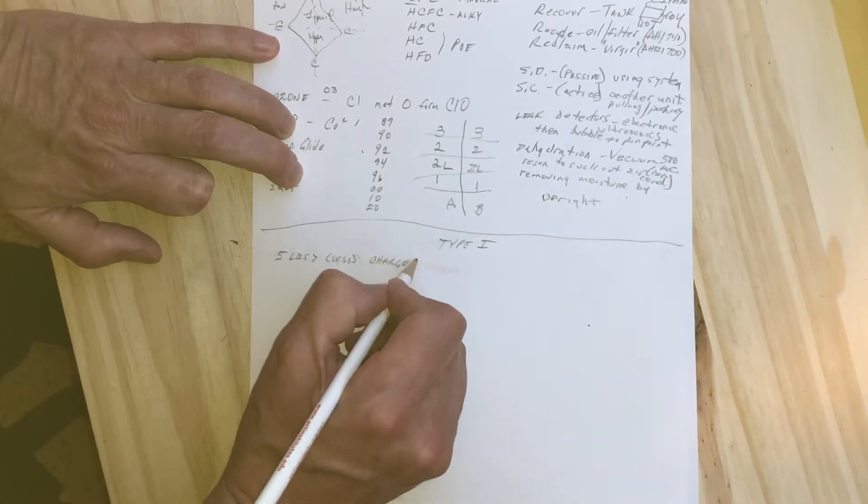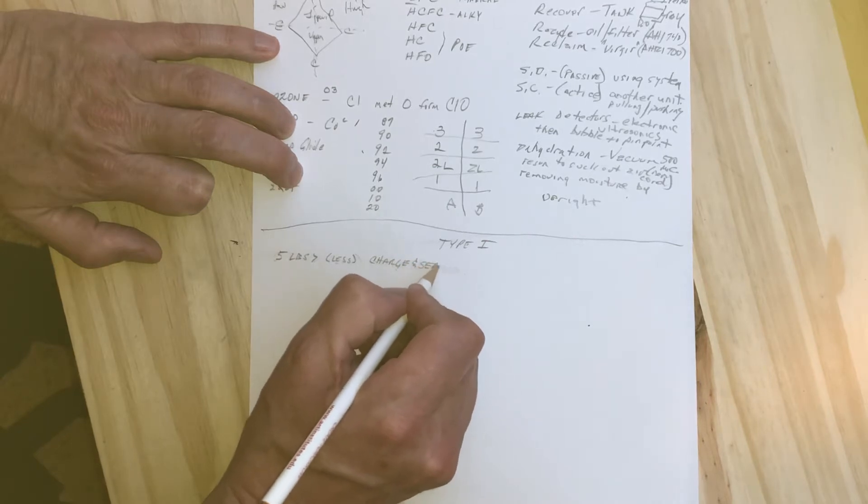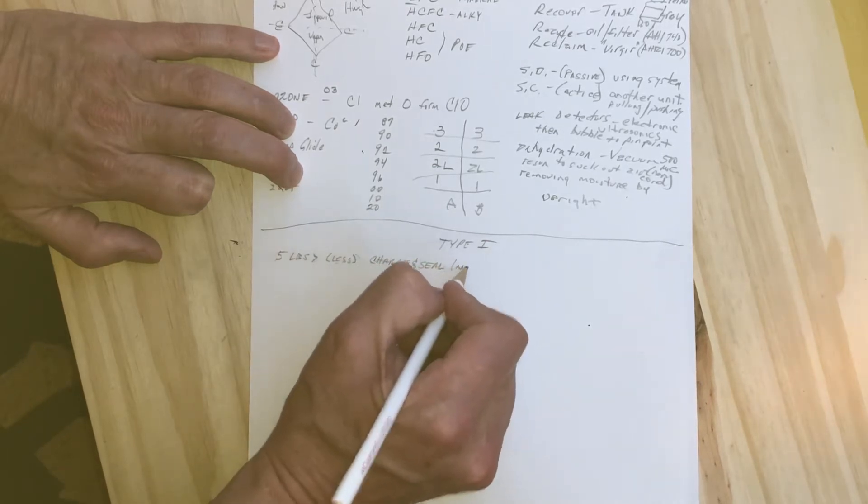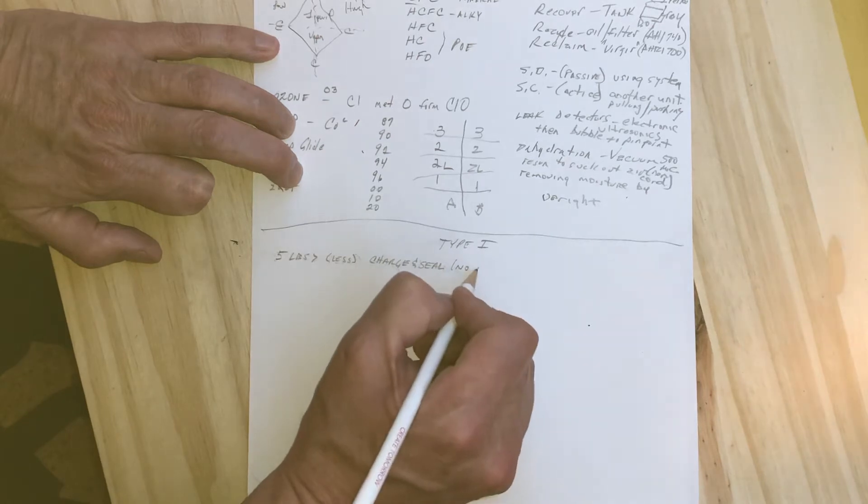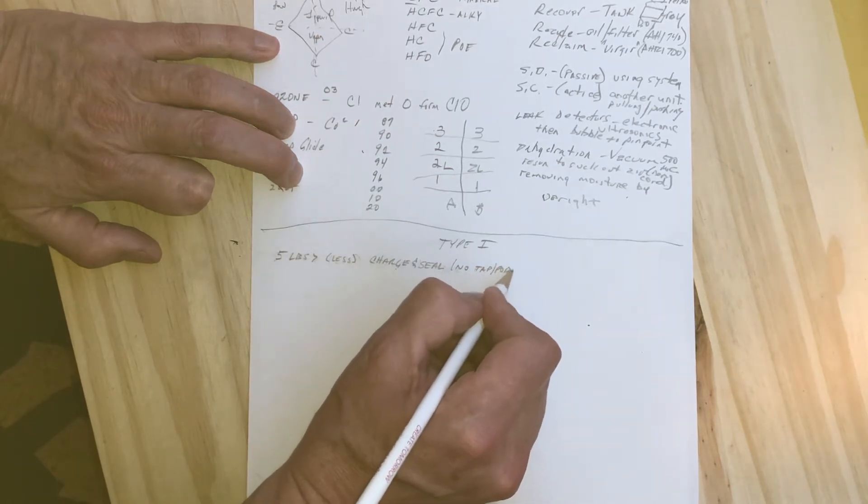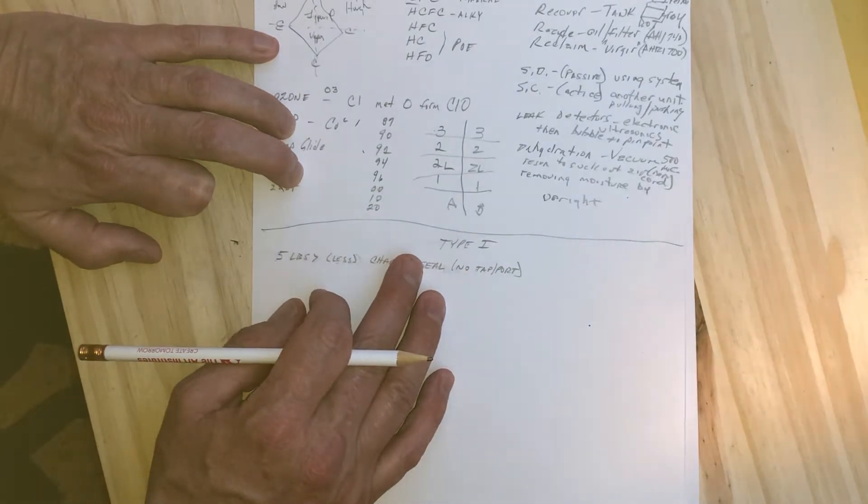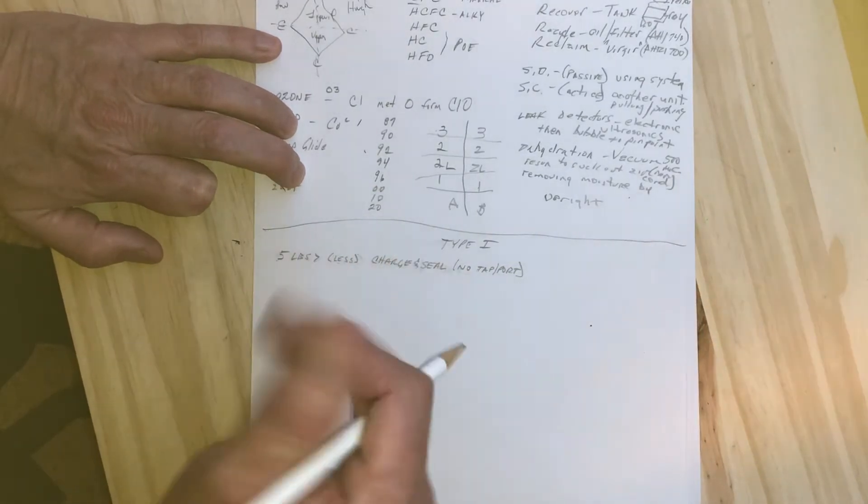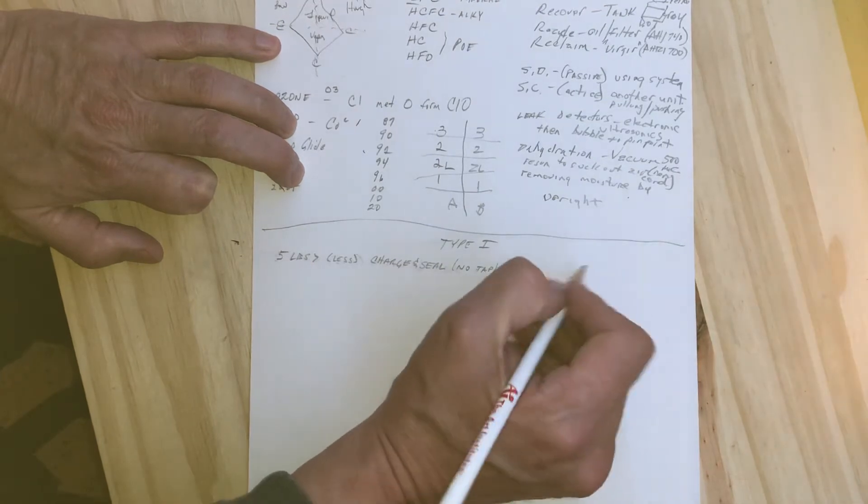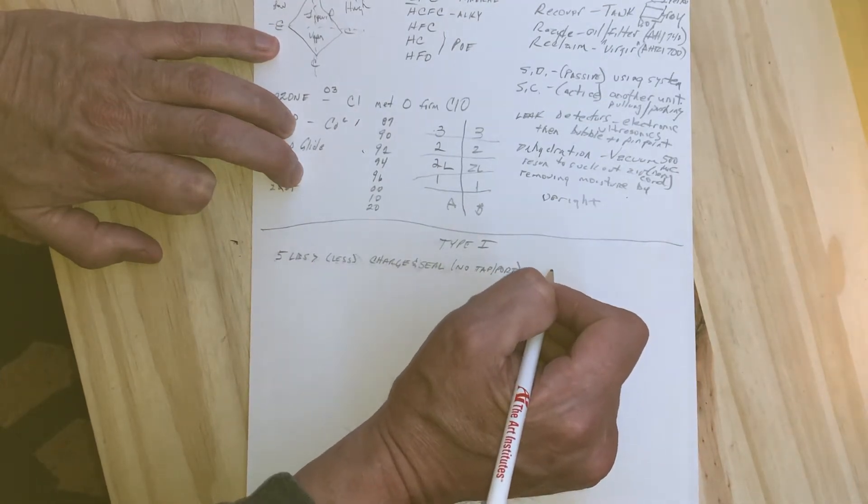It's pre-charged and sealed. The sealing means that there are no taps or ports for us to hook up gauges to, so there's going to need to be some line tap or piercing valve installed that we'll talk about in a minute.